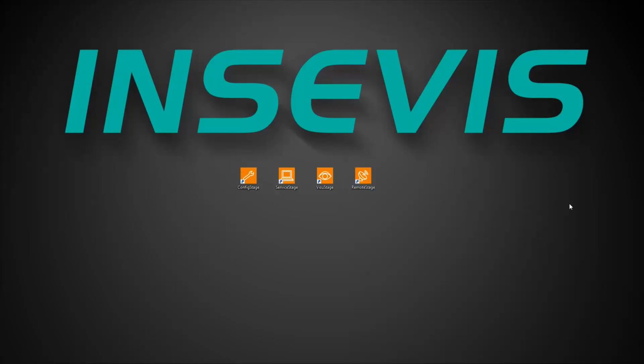One additional thing is the T series of our CPUs has a VNC server inside. So if you want to use maybe your smartphone to monitor your machine, you just download a free VNC client and connect it to your T PLC, and then you have also free visualization. With the difference, VNC is just a mirror of the actual PLC display, and with the remote stage you have a second visualization which is independent from the actual PLC panel. This is also compatible with the existing smart client from Siemens.